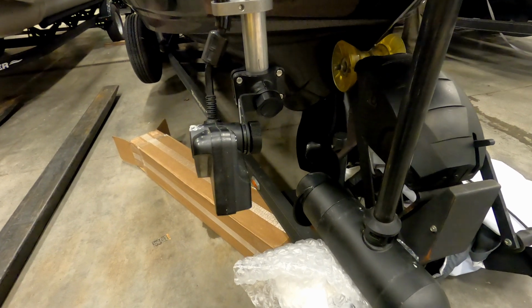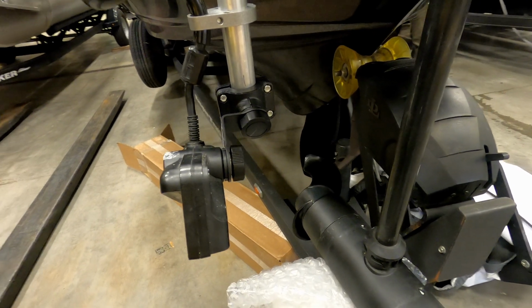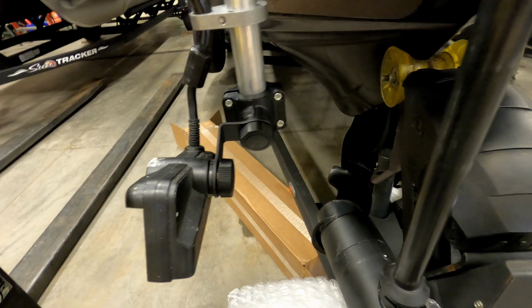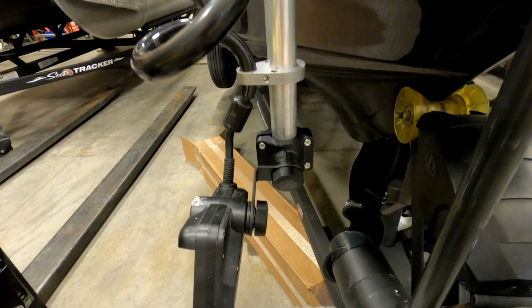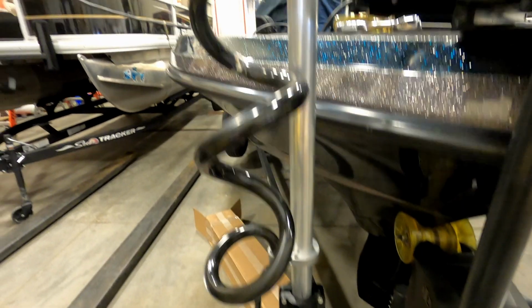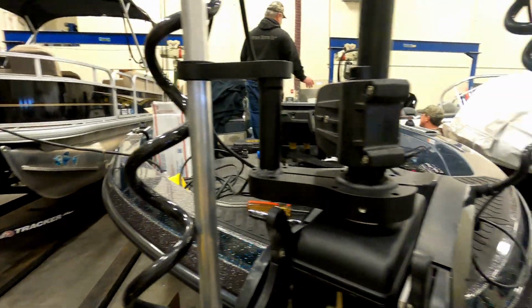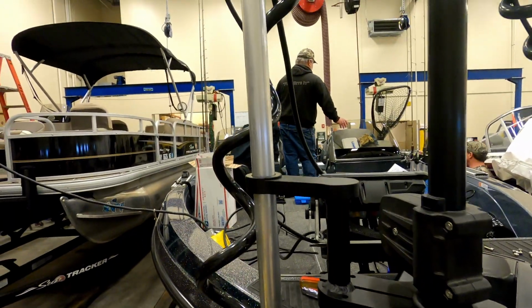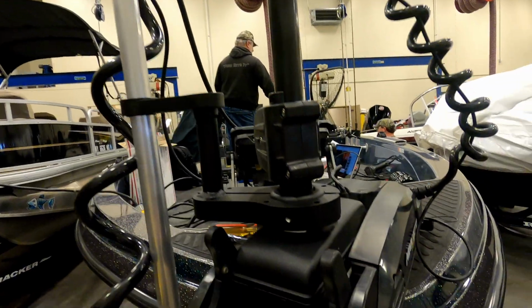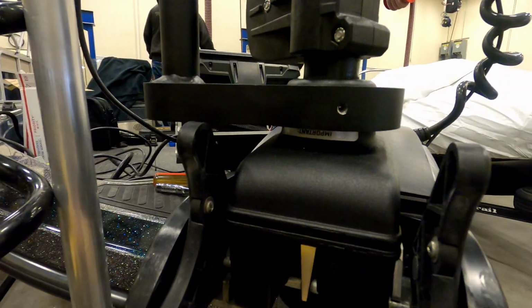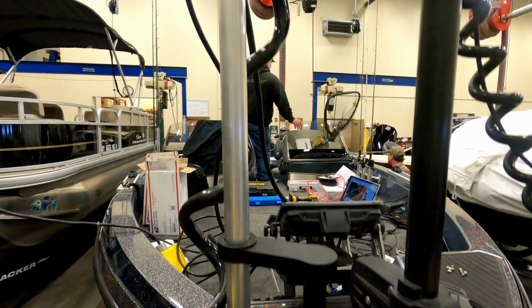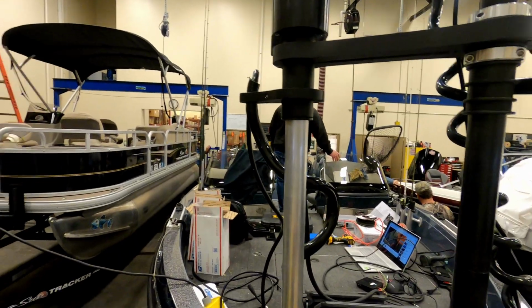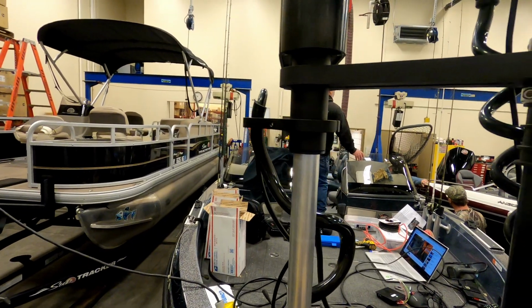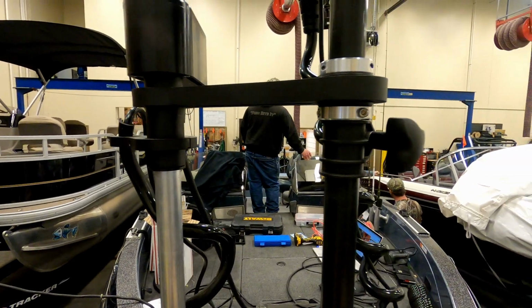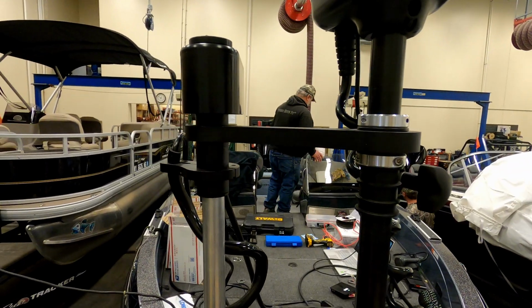Well, there you have it. We've got the live sweep all installed and the transducer ready to go, and you can see the alignment mark on the shaft there, just in case we have to do it again. There's everything. There's a lower mount bracket. You can see how the silver shaft is sliding up and down in the mounts there. Then we've got the upper mount, the cable holder. In this case we hadn't finished tie wrapping the cables, but they are completely tie wrapped now.